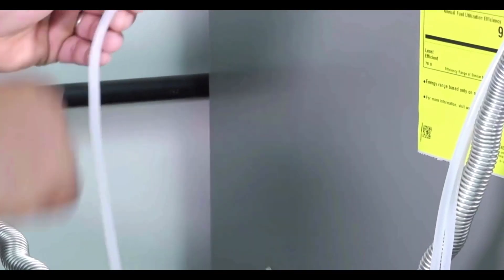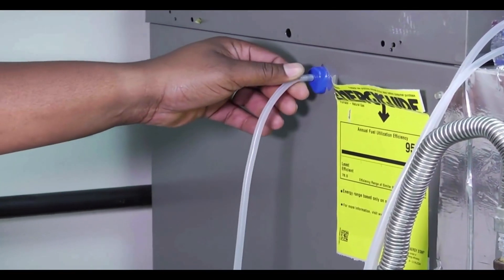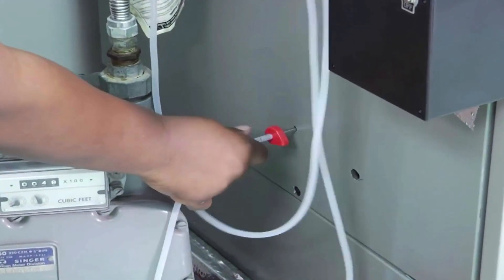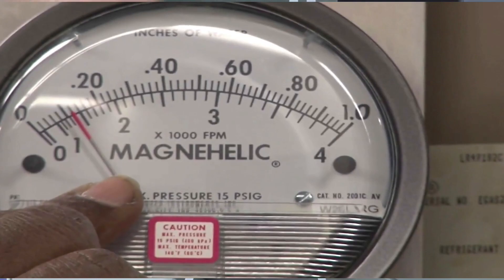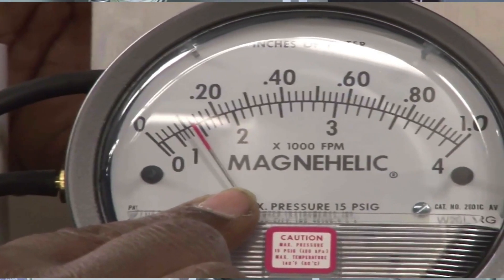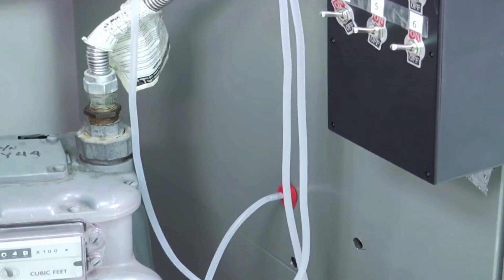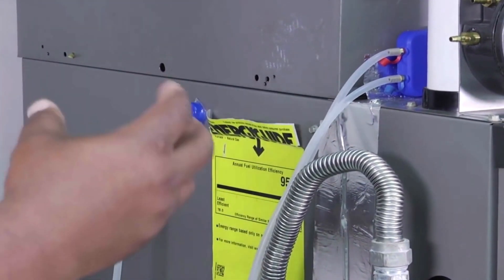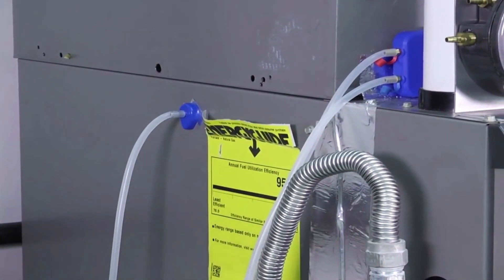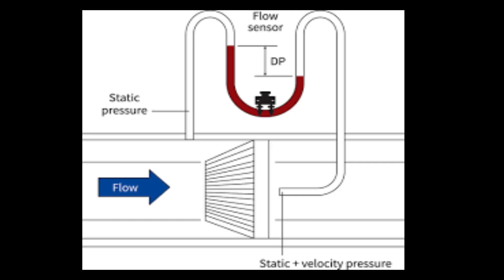Once you get the supply and the return hooked up, you're ready to go. You can either read it directly off the Magnehelic. Essentially, your equipment will have a differential pressure rating that it operates optimally at. If it's not in that range, then you know you've got a problem — it could be a dirty air filter, or something could be clogging up your ductwork. There are many uses for this: you can use it on your AC units, your furnaces, and in commercial applications too. It's all based around airflow — you've got to get the airflow through the system.